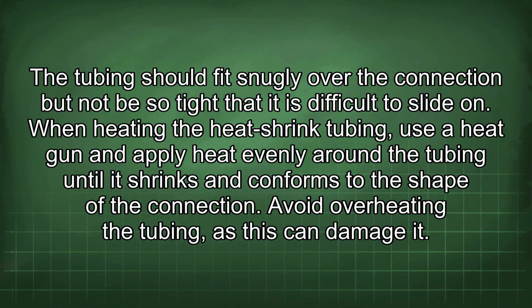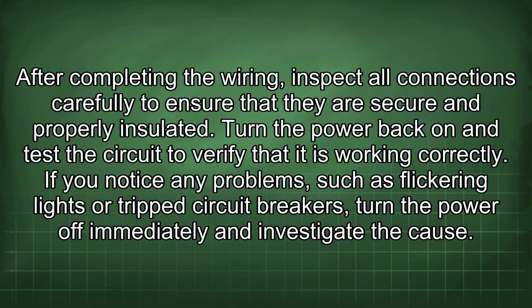When heating the heat shrink tubing, use a heat gun and apply heat evenly around the tubing until it shrinks and conforms to the shape of the connection. Avoid overheating the tubing, as this can damage it. After completing the wiring, inspect all connections carefully to ensure that they are secure and properly insulated. Turn the power back on and test the circuit to verify that it is working correctly. If you notice any problems such as flickering lights or tripped circuit breakers, turn the power off immediately and investigate the cause.